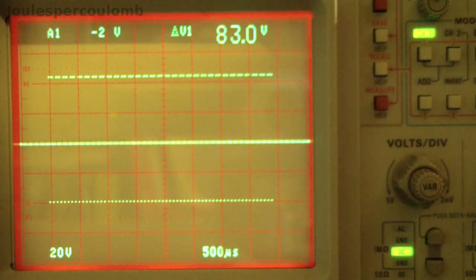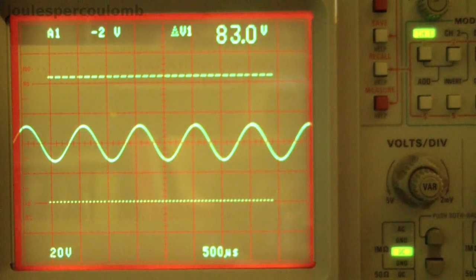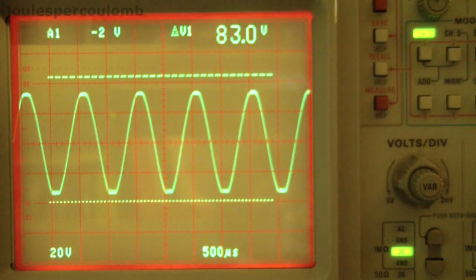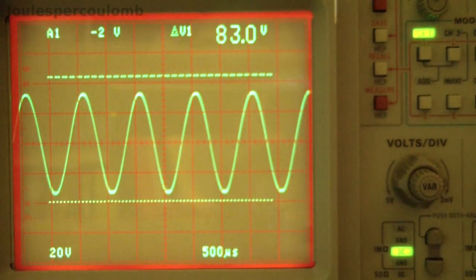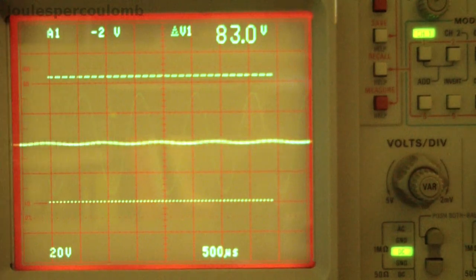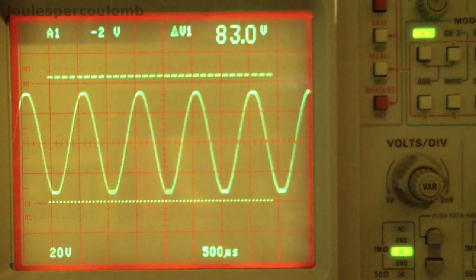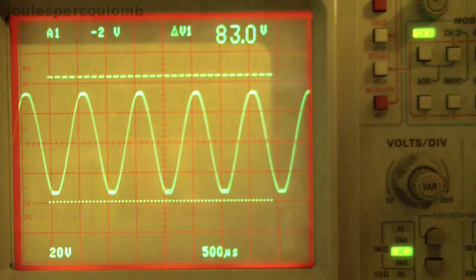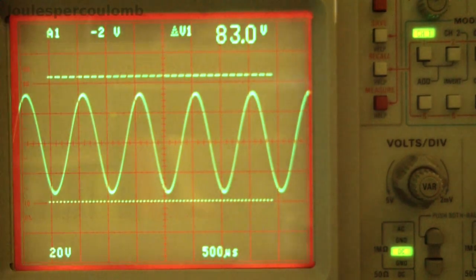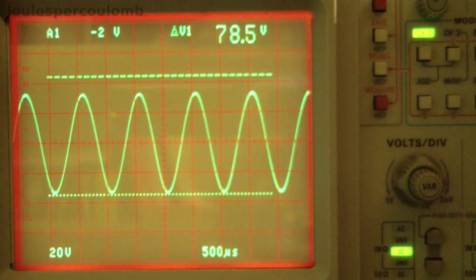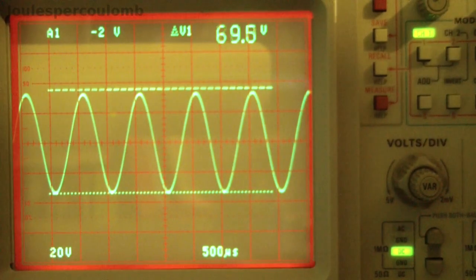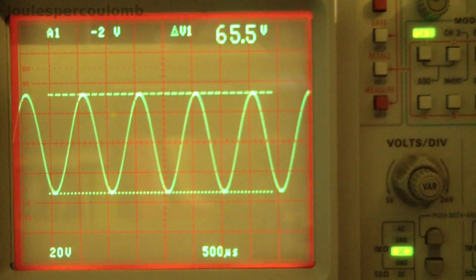The oscilloscope is still connected up to the output of the left hand channel, so I'll turn the volume control up until the signal is close to clipping. About there. I'll move the probe over to the output of the other channel, check that's behaving similarly. And it is, although perhaps it's clipping slightly sooner. So I'll adjust that to there, and we'll measure that peak to peak voltage. 65, 66 volts peak to peak.